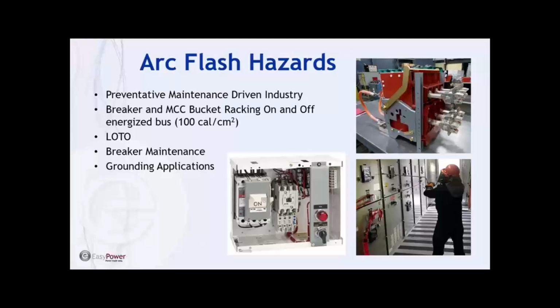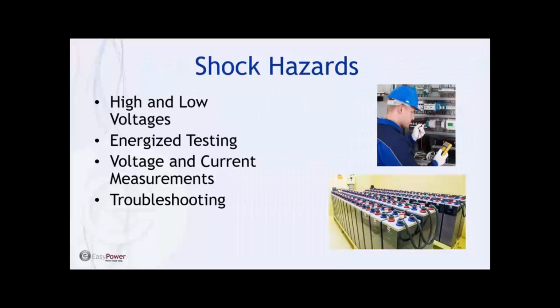In some cases, incident energies could be very high, as much as 100 calories per centimeter squared. We also did a lot of grounding of motors and similar equipment. We maintained and tested, so breakers that energized those motors were racked off the buses and grounding equipment installed. That could be hazardous if you don't install the grounding equipment properly - you could end up grounding your energized stabs inside the switchgear, resulting in a lot of exposure to arc flash hazards when you work in a nuclear power plant. The same applies to shock hazards.